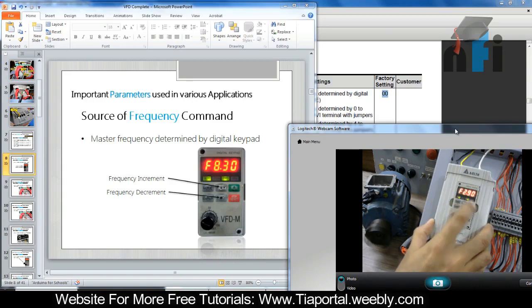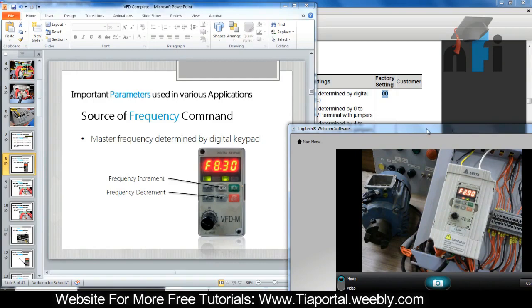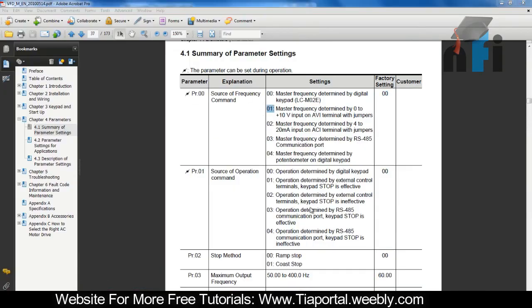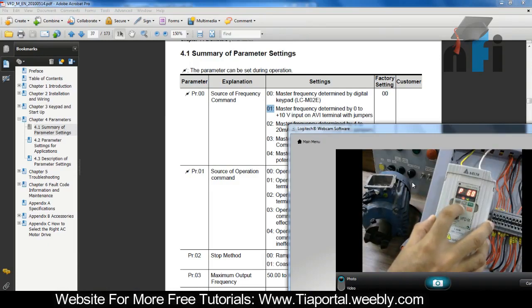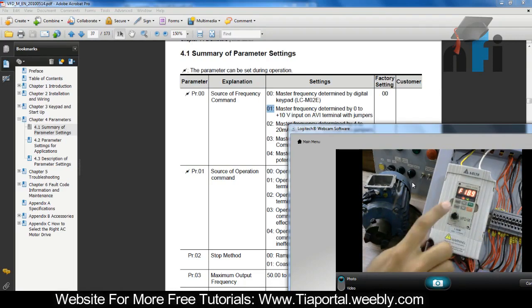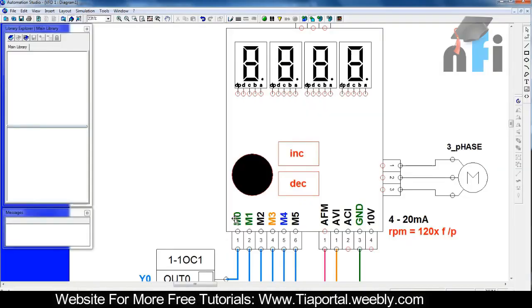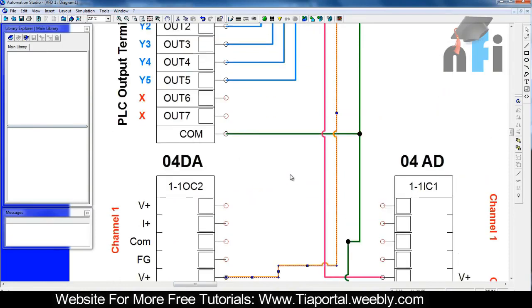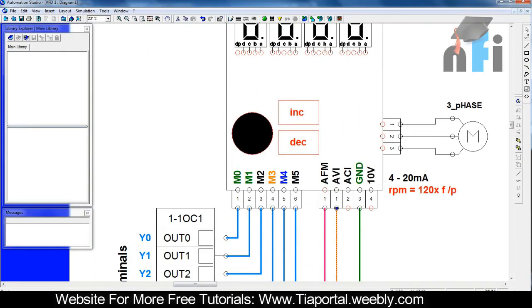The next option says master frequency determined by 0 to 10 volts on AVI terminal. Let's switch over to this mode. For that, in parameter 00 we have to enter 01. Now if you see, the frequency is currently 18.9 Hz - it's not controlled by the keypad anymore. It's getting frequency from AVI, which is connected to channel 2 on my analog output card.